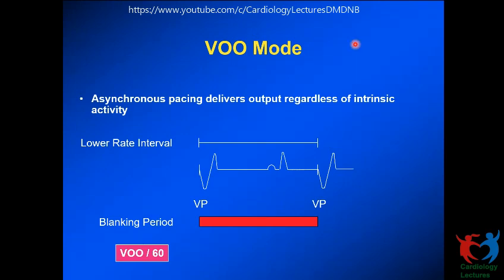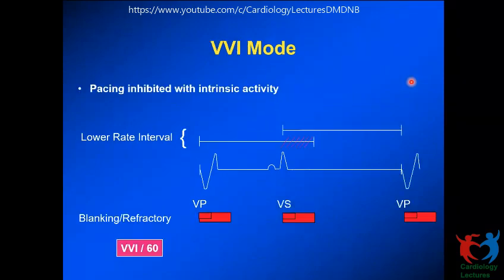When the battery reaches ERI and the magnet is kept, it will not pace at the higher magnet rate. For Medtronic, it is 85. When it reaches ERI, the magnet rate will drop to 65 beats per minute. Both of these are not programmable rates.